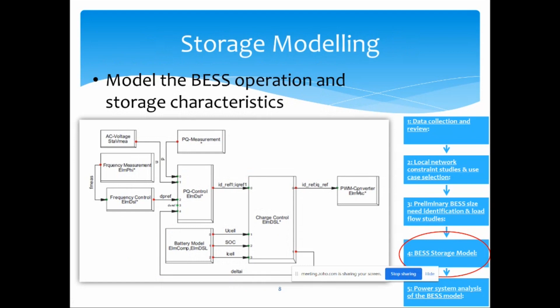On this side you've got your monitoring side, monitoring voltage. It could be monitoring P or Q, active power or reactive power from the network, or frequency, based on the use case you want to apply the storage for. All those measurements go into what's called a PQ controller, which communicates with the charge controller. The charge controller communicates directly with the battery stack, and on that stack the SOC, state of charge, cell voltage, and current from the cells are monitored. That's where you also have characteristics like degradation and round trip efficiencies.